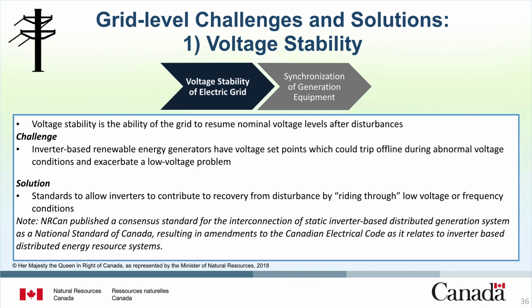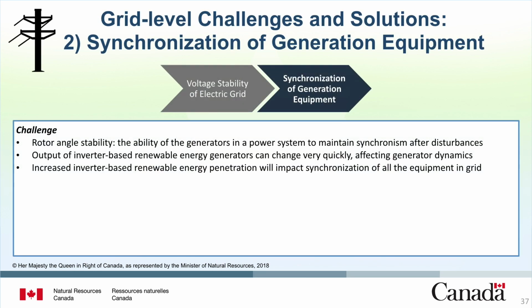Note that NRCan developed and published a consensus standard for the interconnection of static inverter-based distributed generation systems as the national standard of Canada, resulting in amendments to the Canadian Electrical Code as it relates to inverter-based distributed energy resource systems. Next, let's discuss synchronization of generation equipment. Rotor angle stability refers to the ability of the generators in a power system to maintain synchronism after disturbances, such as a drop in frequency caused by addition of a large load or drop in renewable energy output due to natural fluctuation in the renewable energy resource. Output of inverter-based renewable energy generators can change very quickly, in turn affecting generator dynamics. With high penetration levels of inverter-based renewable energy, effects on synchronization of all the equipment on an electric grid may be significant.